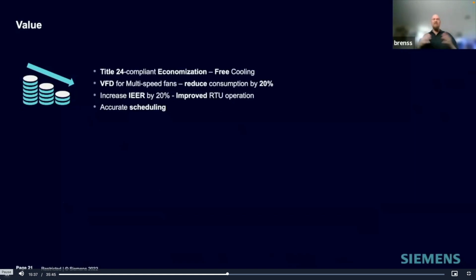The value, Title 24 compliant economization. So what happens is with Title 24, as we might know, is that this is a standard these days. You can't just take a 30-year-old unit that's been sitting on an Army base someplace and put it in a new building. That doesn't work anymore. They must meet standards. So our controller is already meeting the highest standards that are possible. The VFD for multiple speed reduces consumption by 20%. Again, we did an independent lab study for over a month where they ran the unit straight and they came back with 20% energy savings.